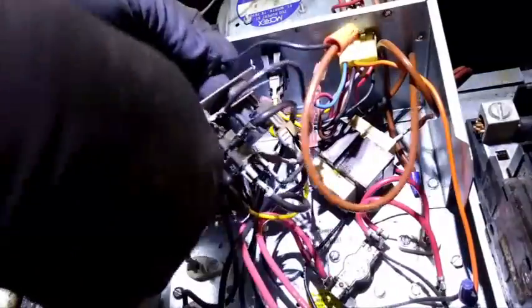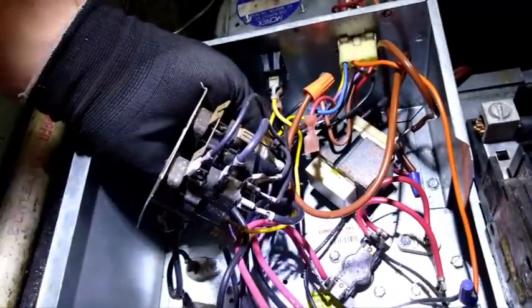I'm taking that—you see that plate there has two sequencers mounted to it, comes as one assembly. Just take that out, because they're timed with specific timing. You can't just put whatever you want back; you have to use that particular sequencer, unless you want to downgrade it to 10 kW and use just a double stack or a contactor.